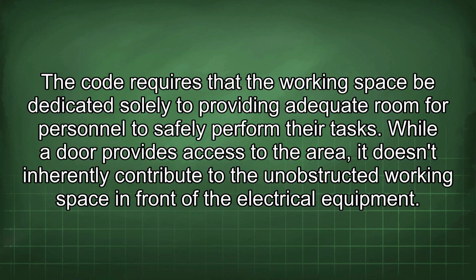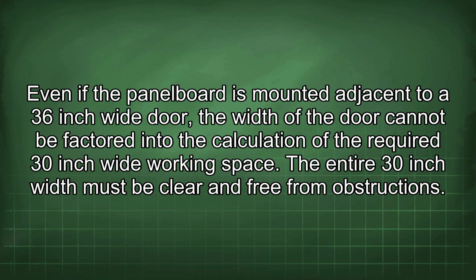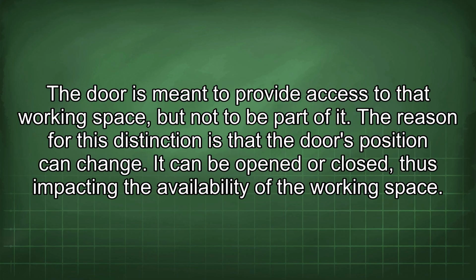The code requires that the working space be dedicated solely to providing adequate room for personnel to safely perform their tasks. While a door provides access to the area, it doesn't inherently contribute to the unobstructed working space in front of the electrical equipment. Even if the panel board is mounted adjacent to a 36-inch wide door, the width of the door cannot be factored into the calculation of the required 30-inch wide working space. The entire 30-inch width must be clear and free from obstructions. The door is meant to provide access to that working space, but not to be part of it.